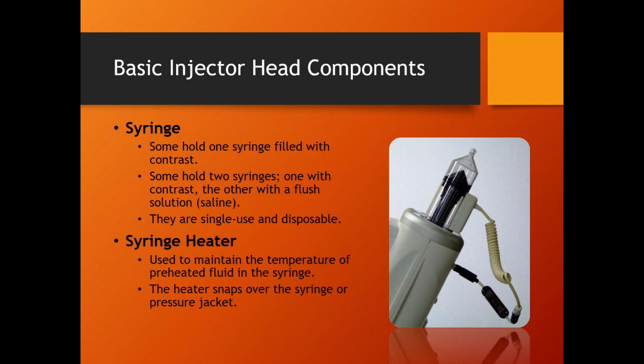We can't have the saline at room temperature, because when we shoot them and they mix together, there's no point in having one nice and heated up and the other one's not heated up. This will cool this off. And then that just kind of kills the purpose of doing this. So if they use heaters, which they don't always, but if they use heaters, they'll have a heater on both sides as well. The saline doesn't need to be heated up for viscosity purposes, it just needs to be heated up so it doesn't cool the contrast off. Yep. It does, yep. You know, there's ports in the back for that. Yep. All right.